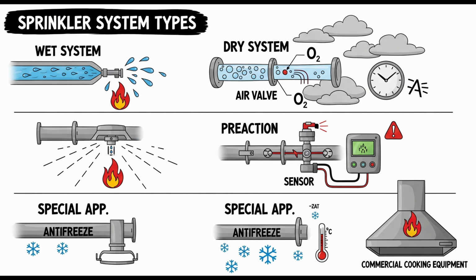Right, less internal corrosion means smoother pipe walls. Smoother pipe walls result in lower friction loss when water eventually flows through them during a fire. Ah, less friction loss. Exactly. This is represented by a higher C value in the Hazen-Williams hydraulic calculation formula, which is commonly used for sprinkler systems. So nitrogen's anti-corrosion property translates directly into a hydraulic benefit. Precisely. A higher C value can mean you might be able to use smaller diameter pipes for the same flow, or run the pipes longer distances, while still meeting the required water flow and pressure at the sprinkler heads. It can make the hydraulic design more efficient.